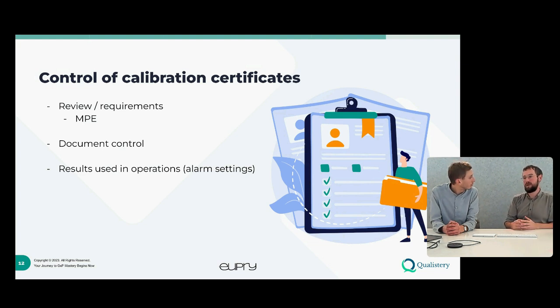We even see customers on the opposite end, setting requirements very, very tightly, expecting very precise equipment for processes that don't really require it. So first, set your requirements, which follows what calibration points you choose. In general your calibration points should cover from below your operation temperature to above it, with one in the middle, or you can cover a larger range if we're talking a fairly small range of temperatures.